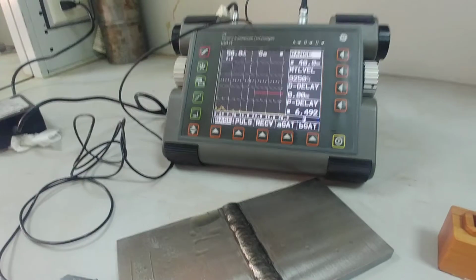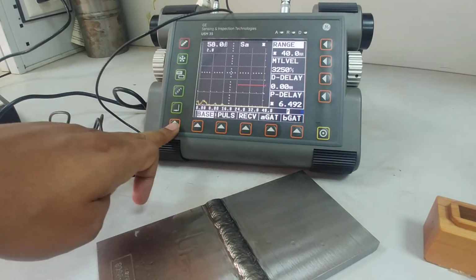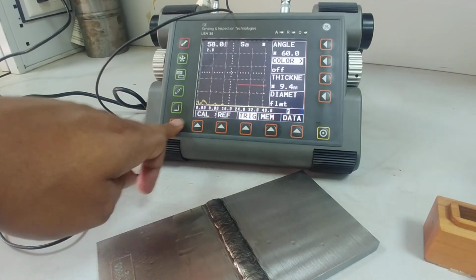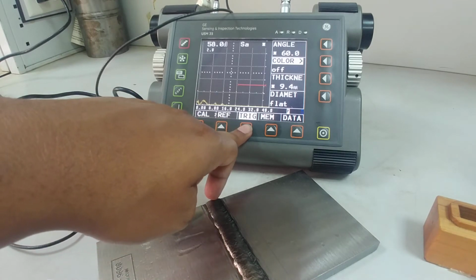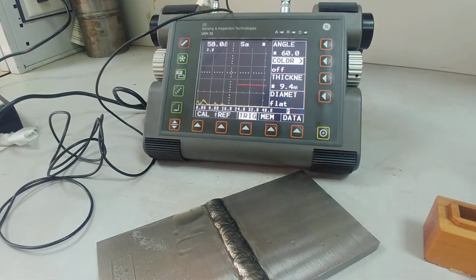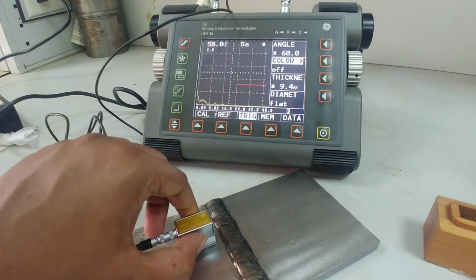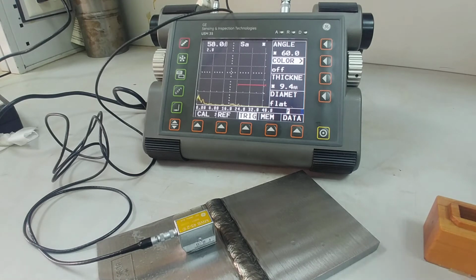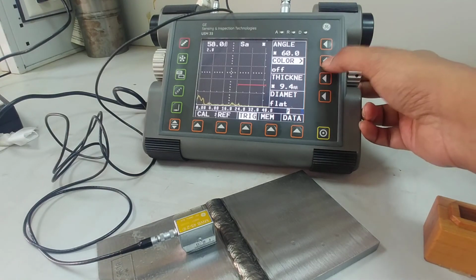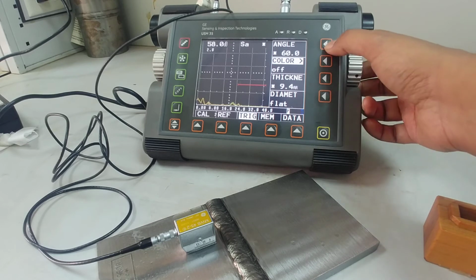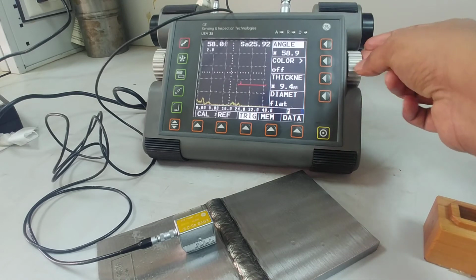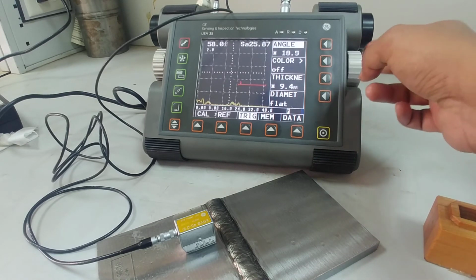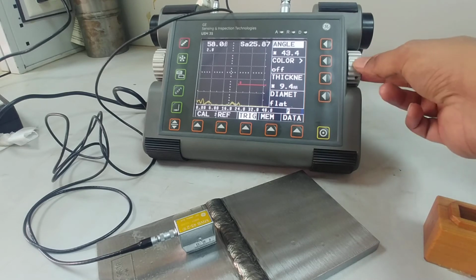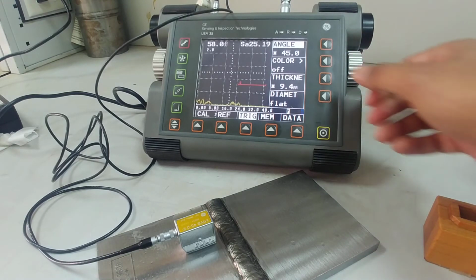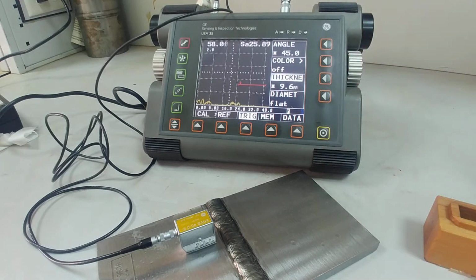Now I just want to show you something. Another feature of this machine is a trigonometry function. I can use this function so that it gives me the direct value of the defect depth. I don't need to do the calculation. First you have to set the angle. What angle are you using? Same angle, like you're using 45, so set it to 45. Then set the thickness, 9.6.